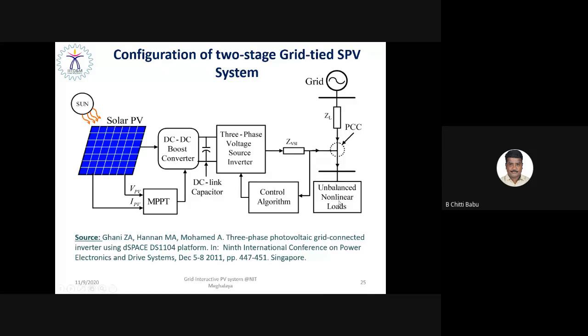requirements. So when you connect a three-phase non-linear unbalanced load at the point of common coupling, of course, as the non-linear load interacts with the grid, ultimately the grid current is going to be distorted. In addition to the distorted grid current, the voltage profile at the point of common coupling is going to be reduced, right? So the control algorithm employed on the grid interactive three-phase voltage source inverter has to ensure controllable active and reactive power for voltage as well as frequency control. That is very much essential.